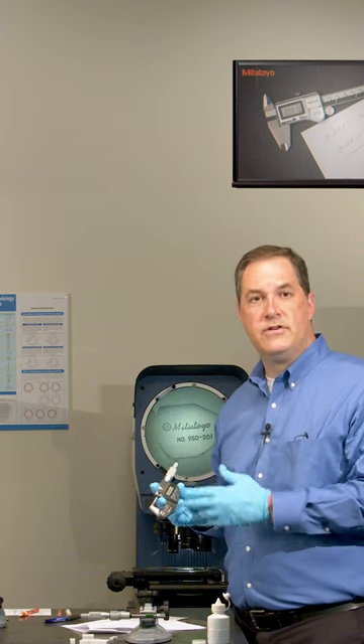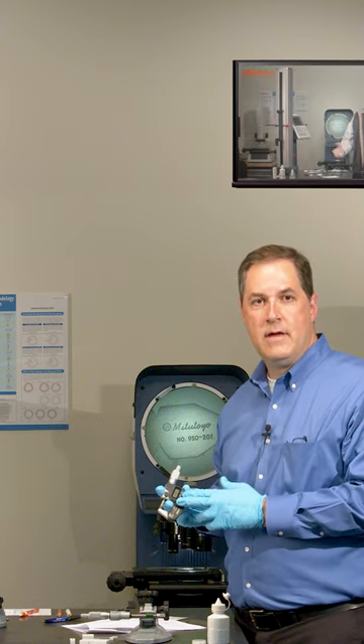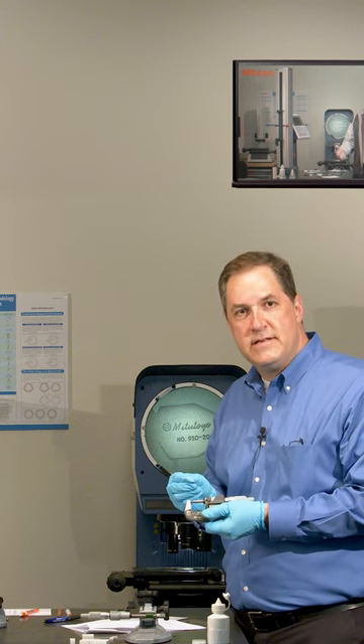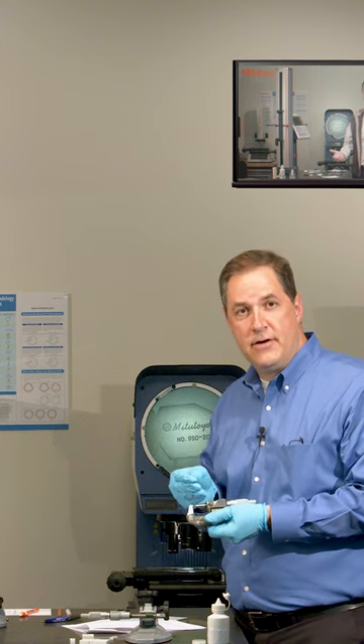So that was the calibration of a 0 to 1 inch micrometer. Now in a 0 to 1 inch micrometer, we can bring the measuring faces together to set the zero.